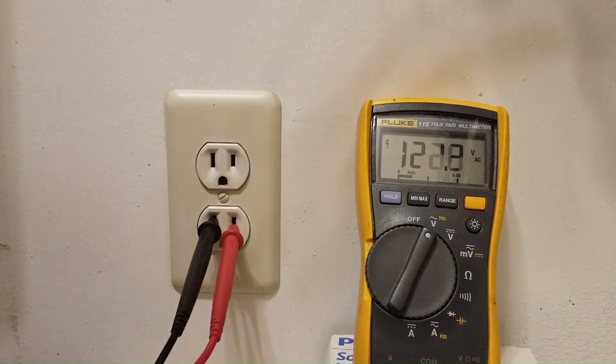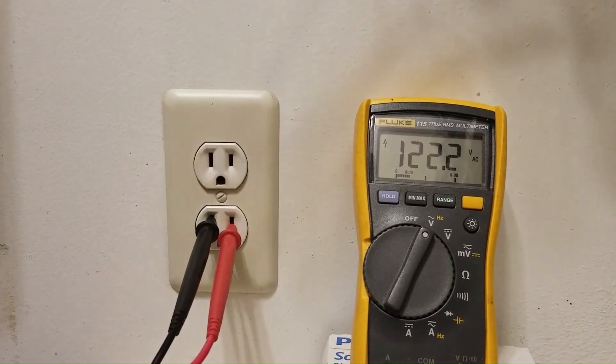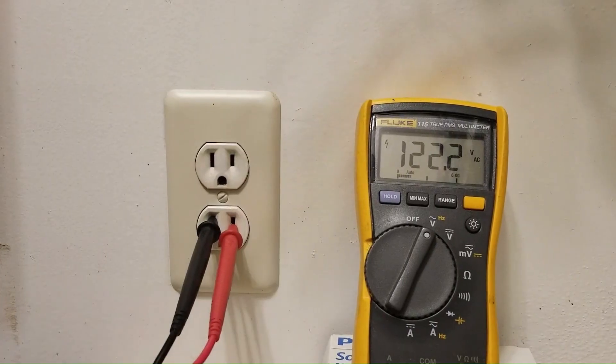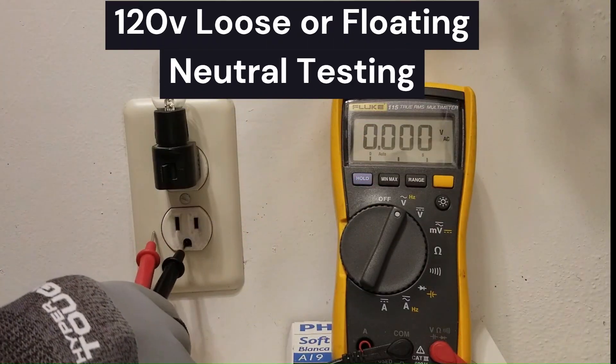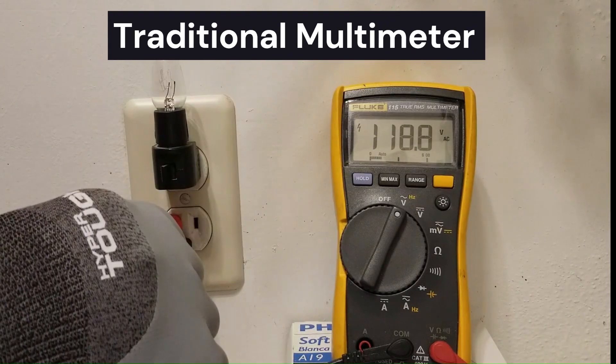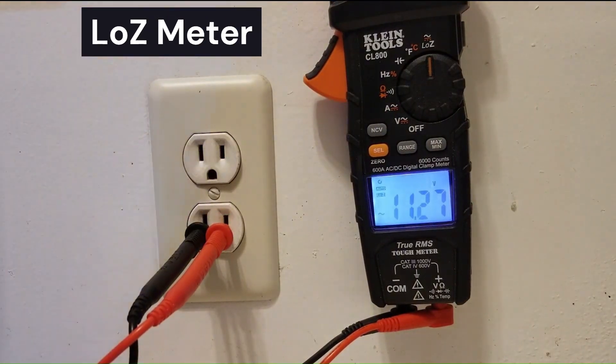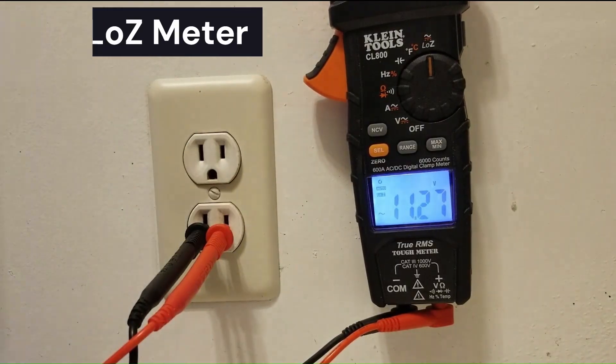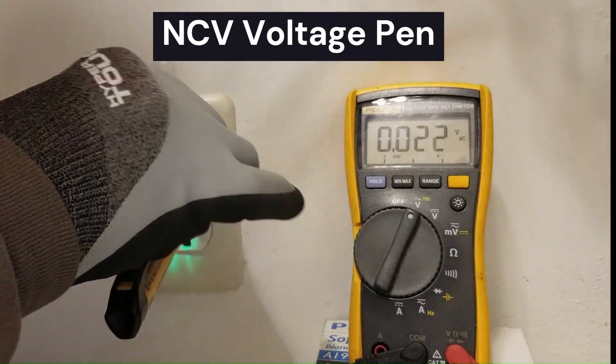When I pull the light bulb out, it goes back up to 122 volts. So why is that? In this video, I'll show you how to test for a loose or floating neutral using a traditional volt meter, a low Z meter, and a non-contact voltage pen.